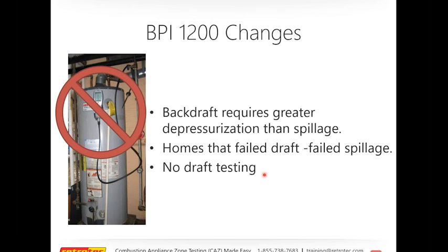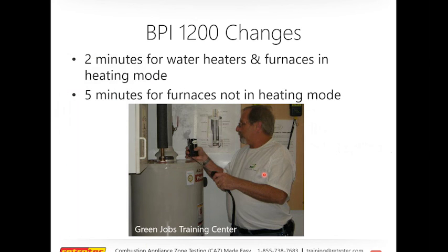So there is a question here asking specifically. Matt is asking specifically about this slide. So Matt, I'm glad you asked. Matt says, if I'm not mistaken, the 5-minute spillage for cold vent says except for domestic water heater, or DWH. The domestic water heater follows the 2-minute spillage mark. That's how I read it. And essentially, Matthew, I'm sorry, that's right.